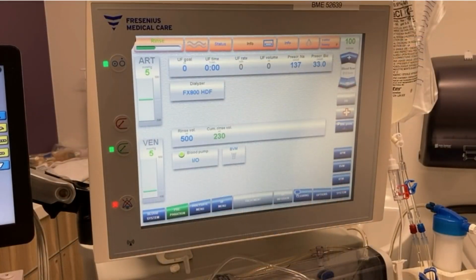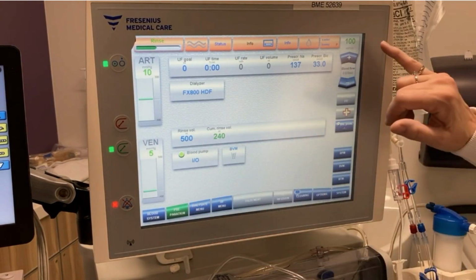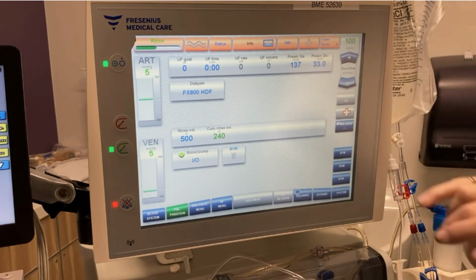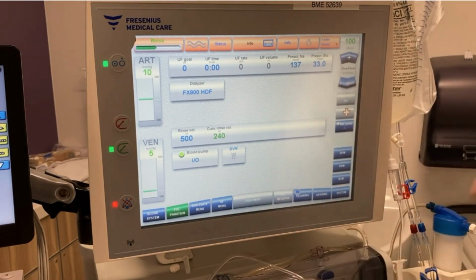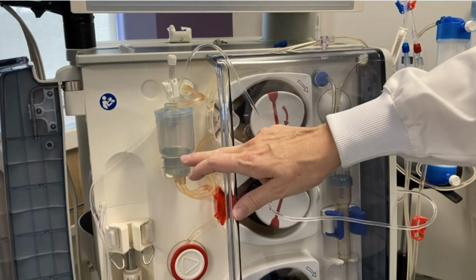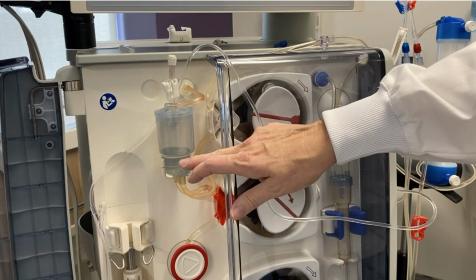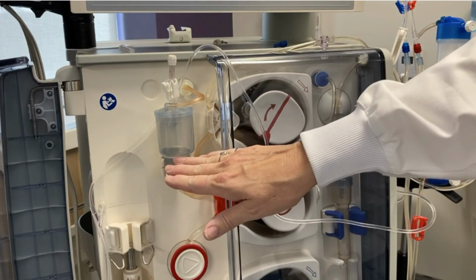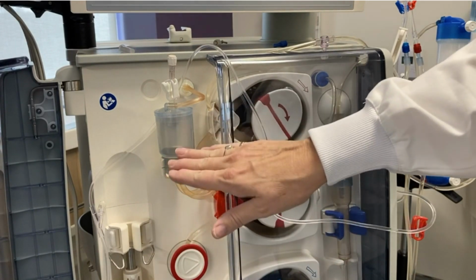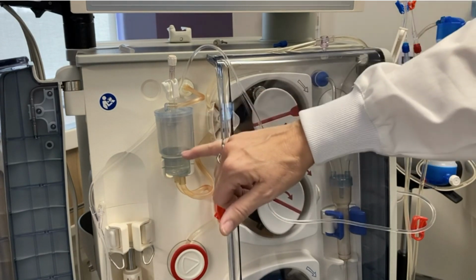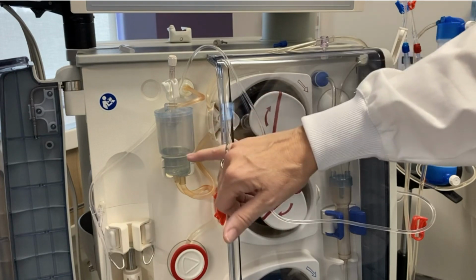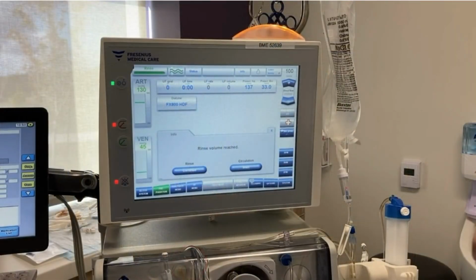So just as with the standard setup, your rinse volume is 500 at 100 mils per minute. So it takes you 5 minutes to prime your complete set. So just to make a note of the level for the arterial chamber, it should be just at the bottom of the arterial chamber so that it leaves a lot of room for fluctuation when you're doing dialysis.